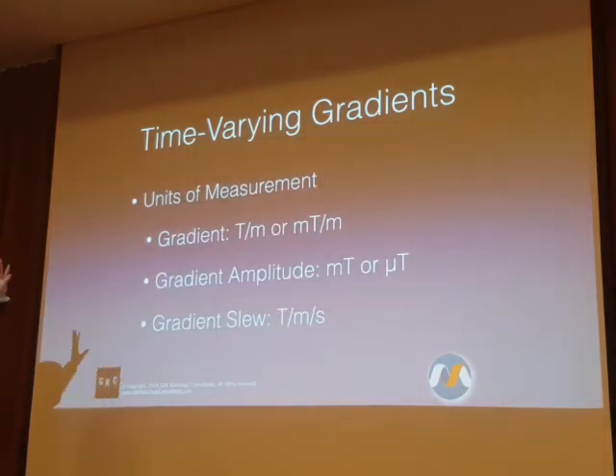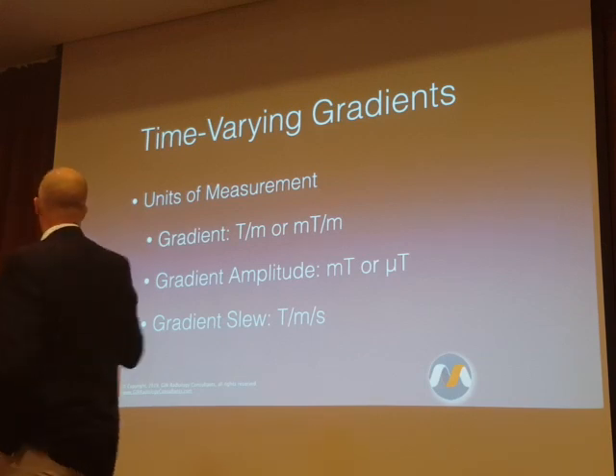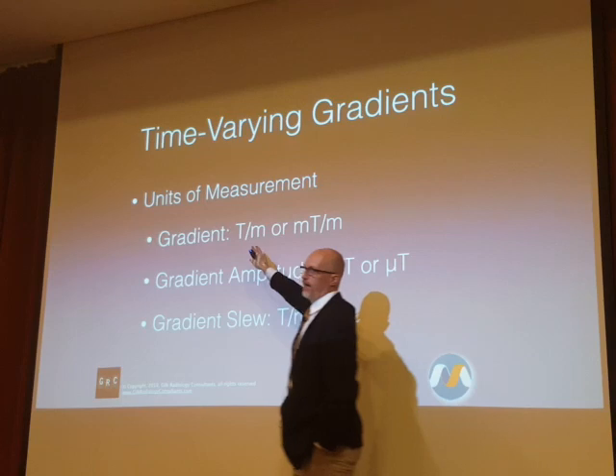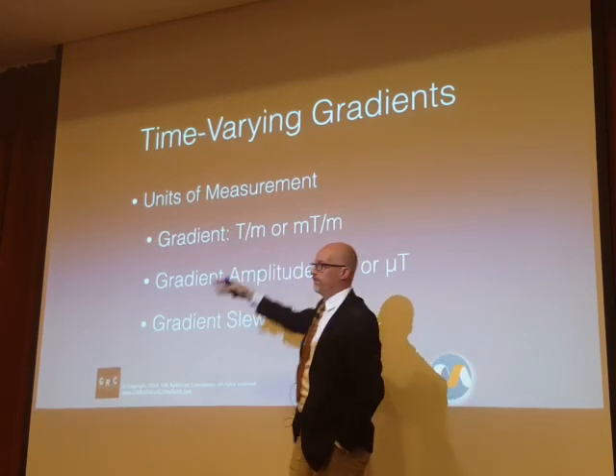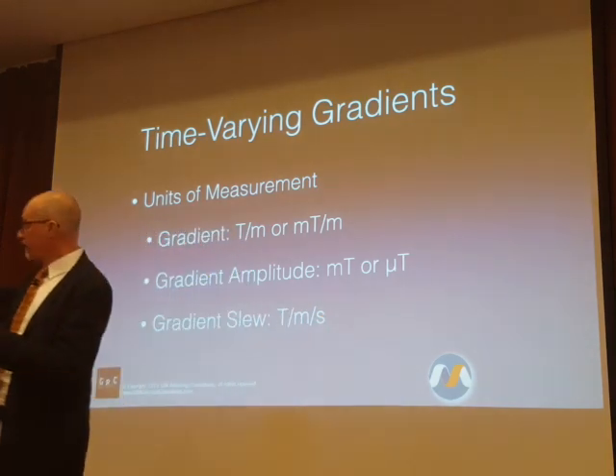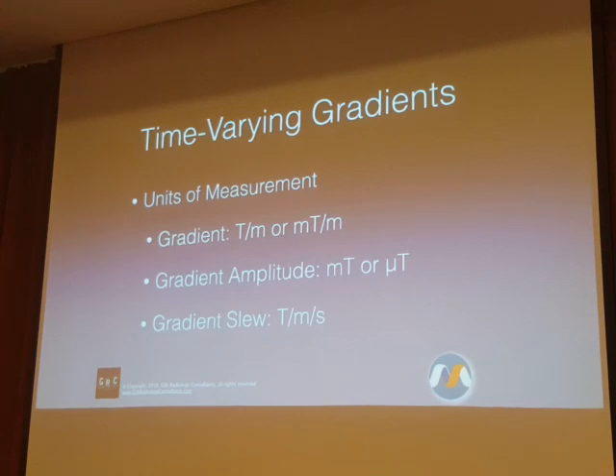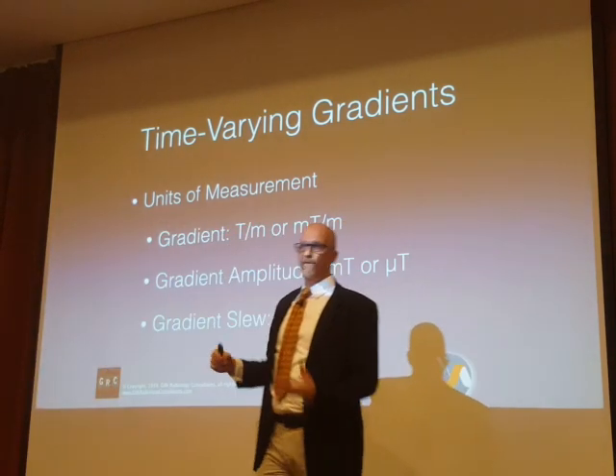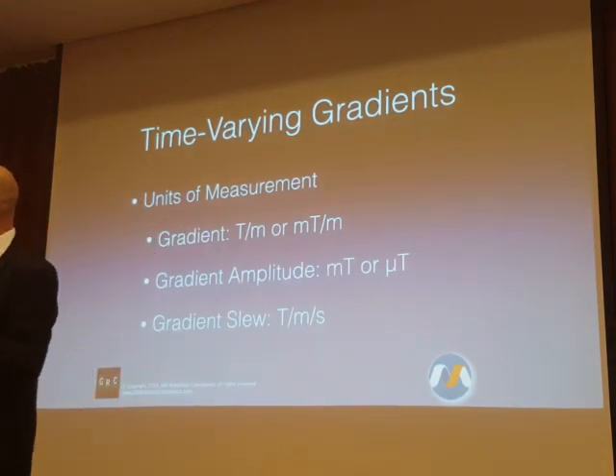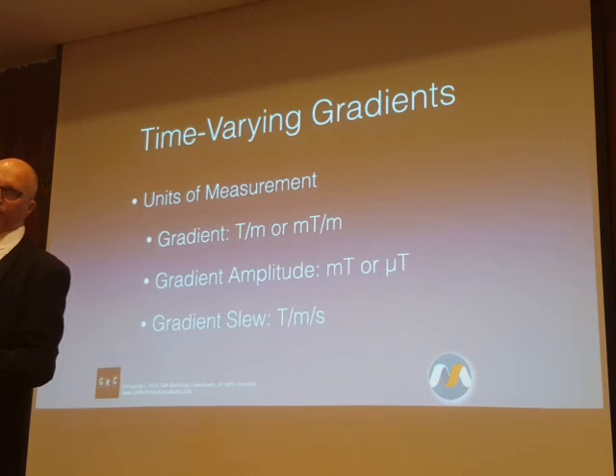So the units of measurement. Gradients are very tricky because we use the same term to really mean 3 separate things. There is the gradient slope, the rate at which the gradient changes as we move away from isocenter in any direction. And that's probably the most frequently reported unit for the gradient. Tesla per meter, millitesla per meter, essentially defining how much does the static field change as we move away from isocenter. Gradient amplitude is the second most common way that I think this is reported, and that's at the furthest point, what is the maximum change in the static field?